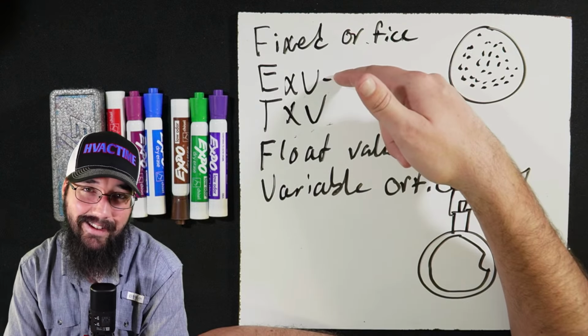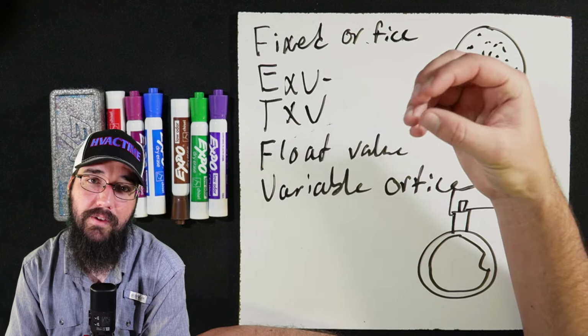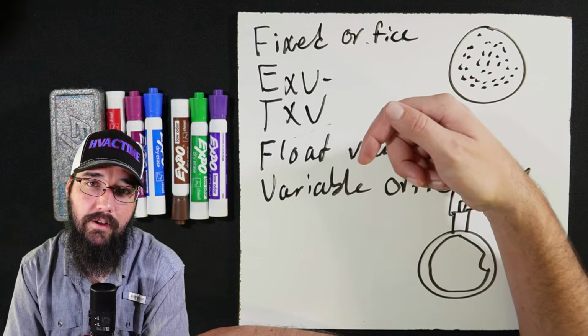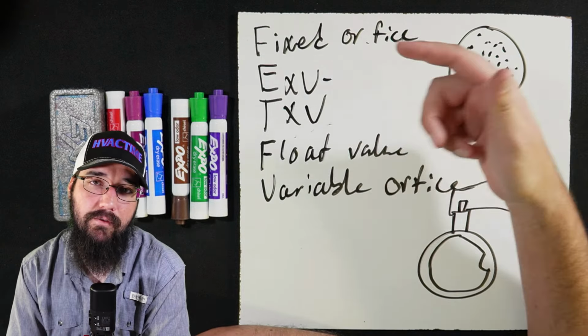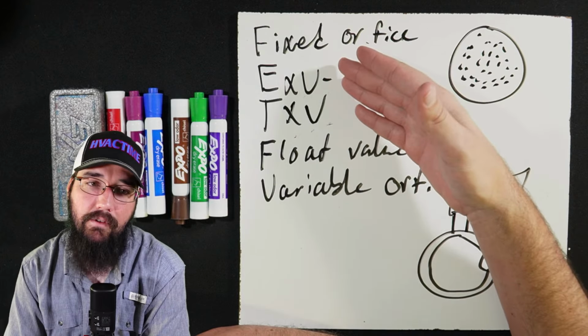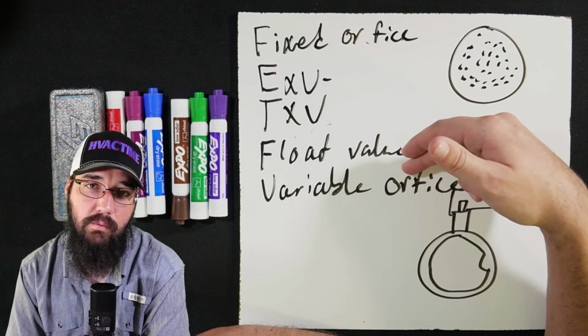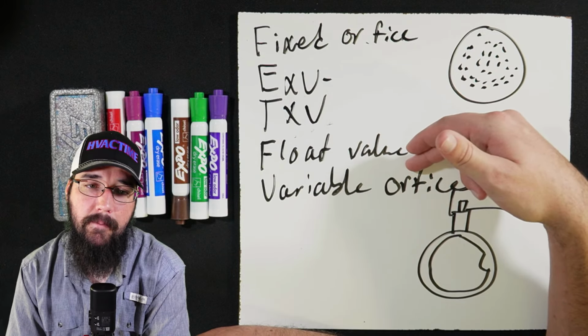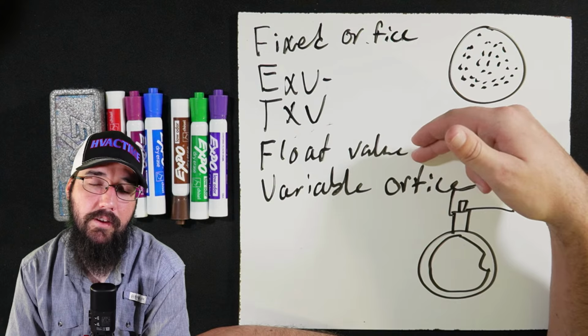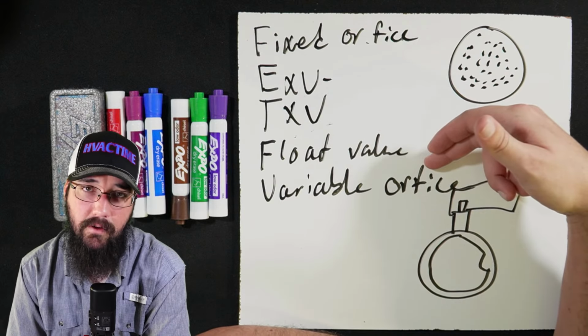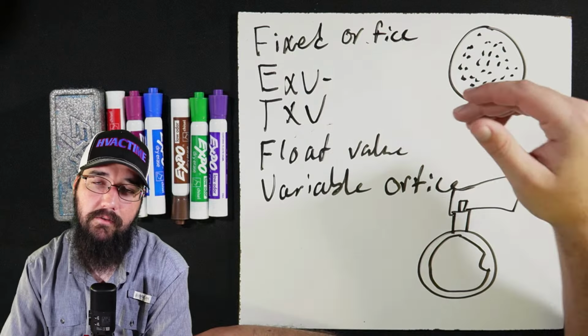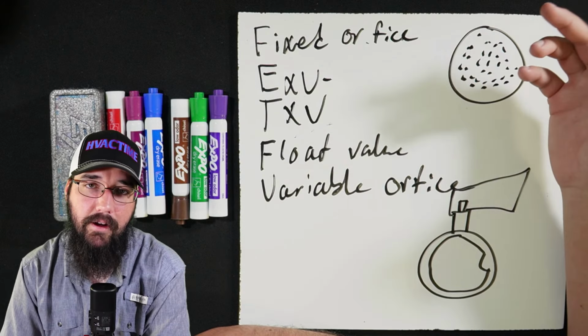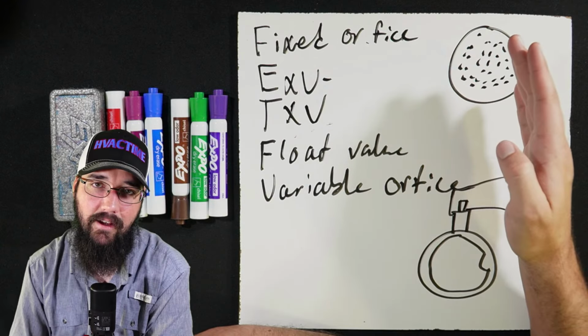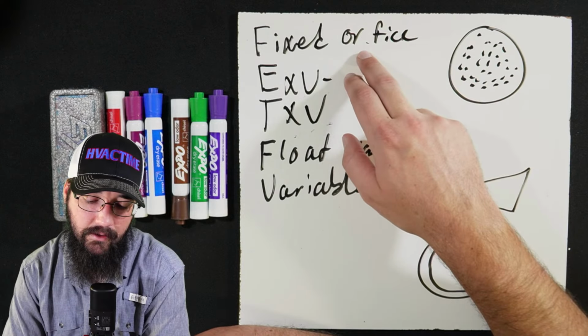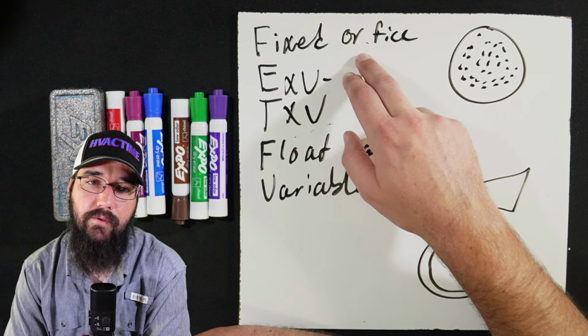They could technically make a multi-head EXV block work at those tonnages, but then they'd have to rewrite everything for that, versus they just make a smaller orifice. They just make this smaller, and then they don't have to change anything. They just make it smaller, and then it can scale to the size they need from there, and they keep a consistent design. Same thing with these Trane with a fixed orifice.